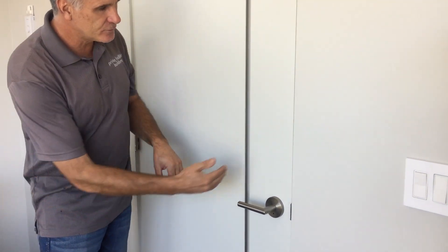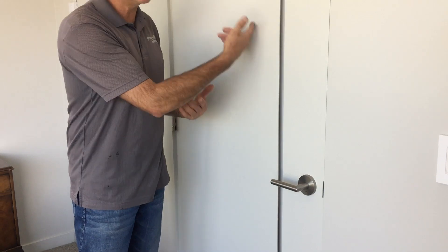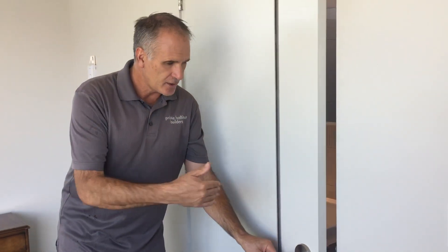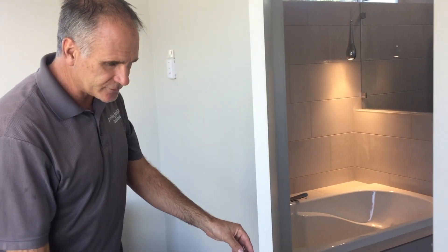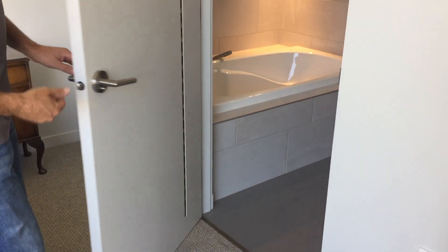The air can actually move from this positively pressurized room — it's not high pressure, it's very, very small pressure — but the air moves through this door. It also acts as a sound baffle. This is an ensuite on the other side. Air travels through these doors, and it also travels underneath, but we don't need a great big gap underneath when we have the Van Air door like this.